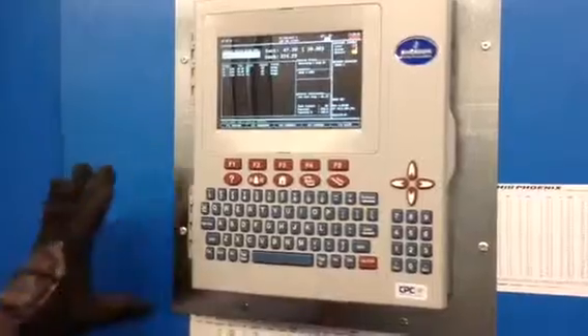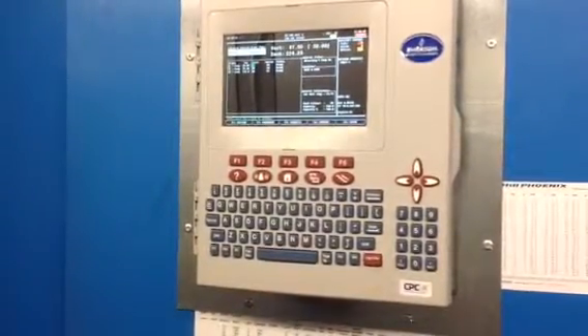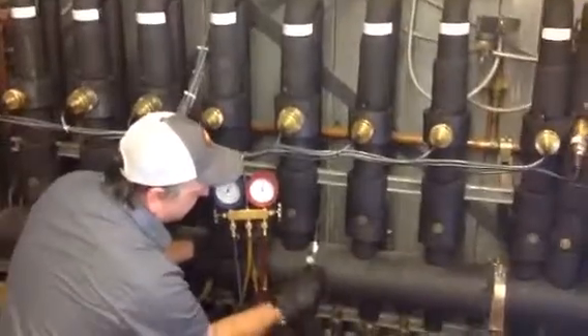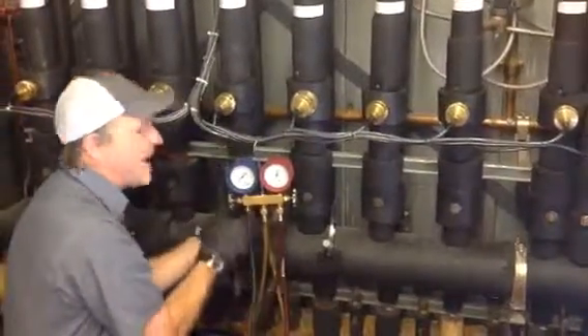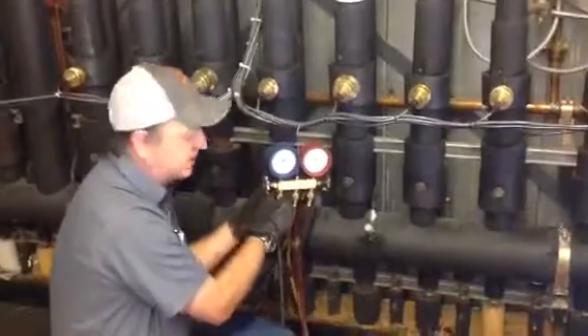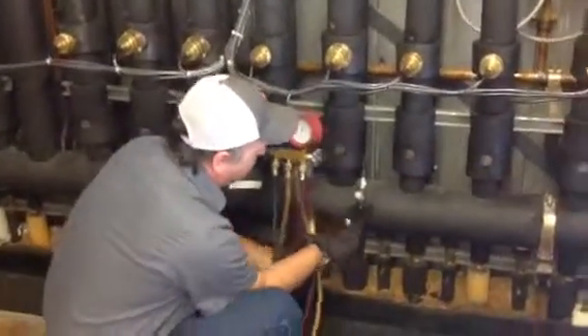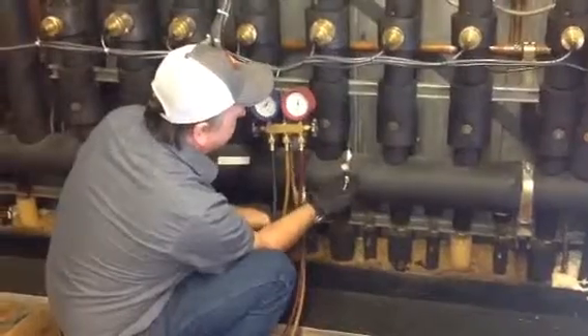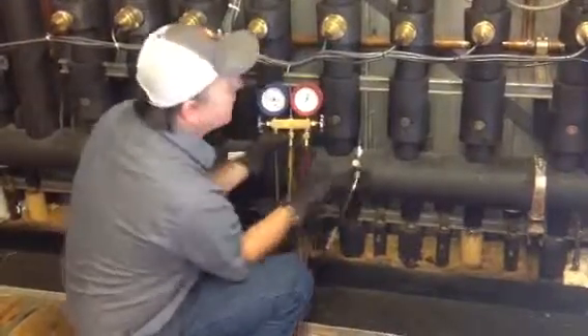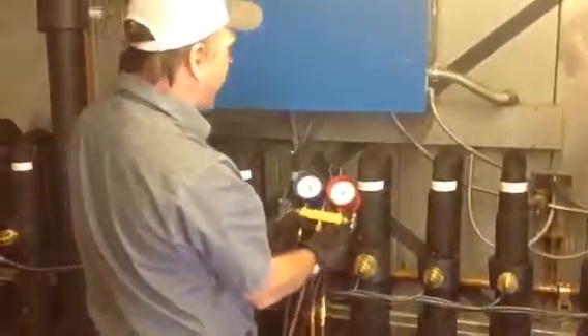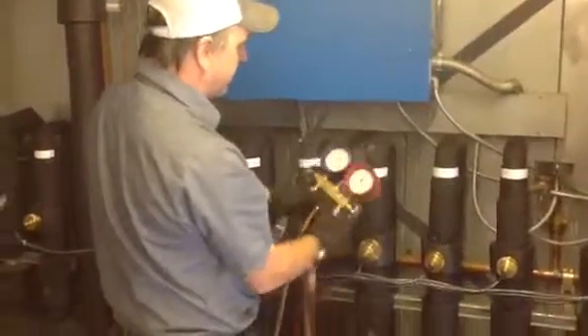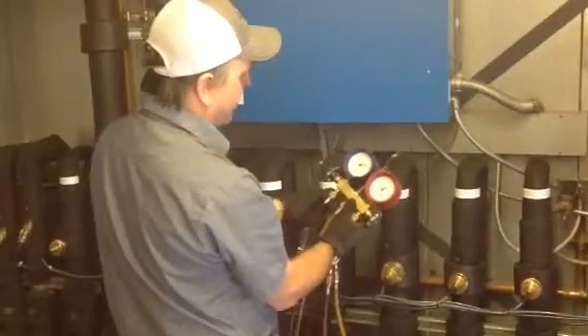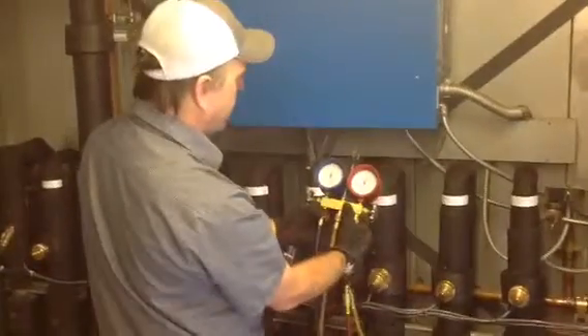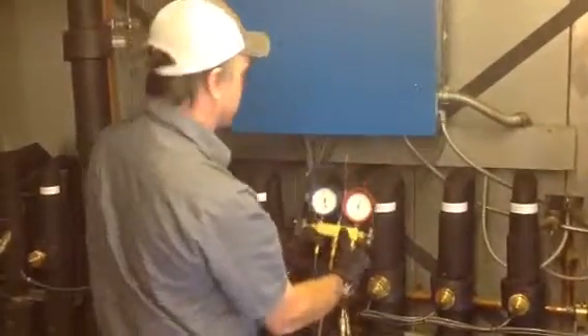Once we know what suction pressure the controller's saying, we need to go find our suction transducer, which is over here on the suction header. I like to put mine on my gauges, that way I don't lose it. Now we look at our gauge reading and see what we have. Gauges are closed, hoses are tight, bleed the air off a little bit, and read it. This is showing 50 pounds.